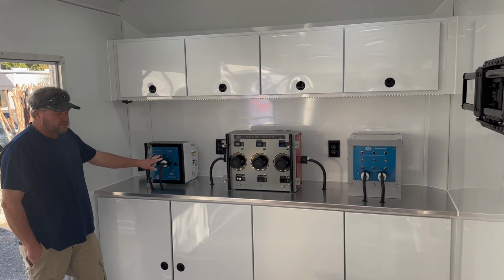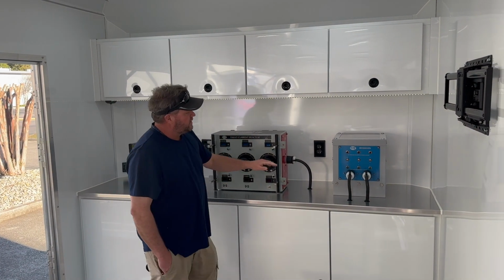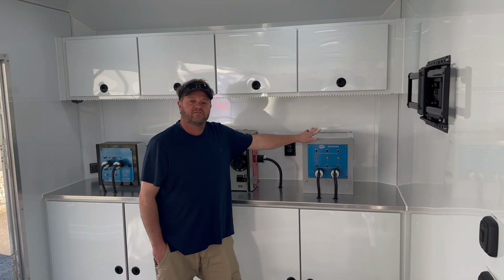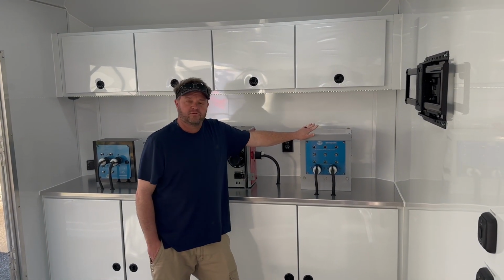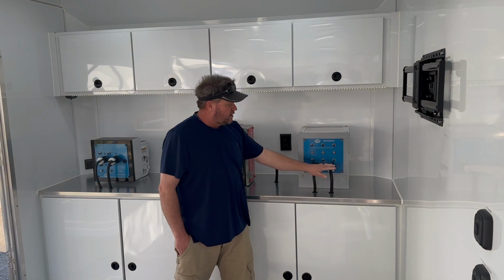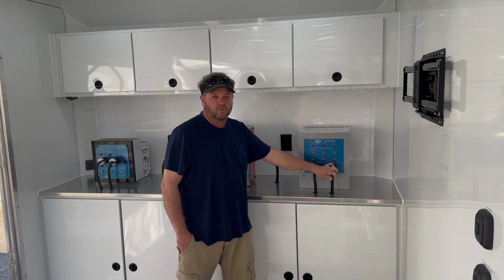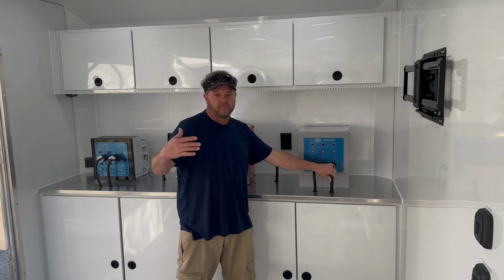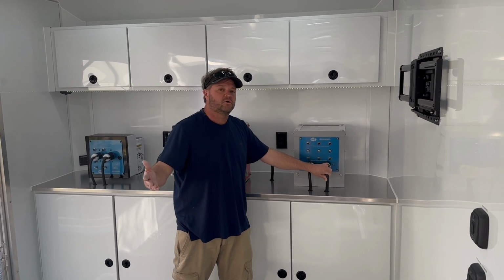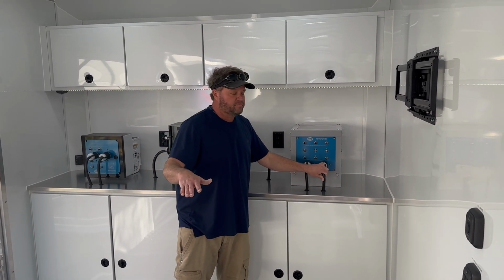From this point, once it leaves the phase converter, it comes into the transformer over here. This is our three-phase transformer. It comes in 240 delta and comes out 120/208 Y system. That is what our model is based on, a 120/208 primary Y system.